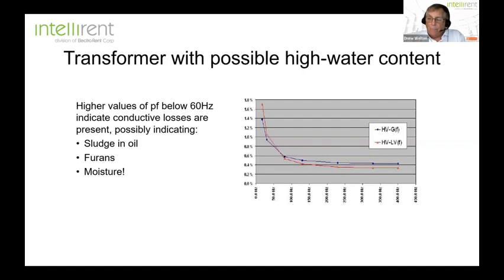your dissolved gas analysis shows an elevated amount of moisture. Okay, it shows a high ppm measurement. And let's say that your power factor also shows that you have conductive losses. Well, you could very well have a moisture issue. Okay, but we're going to take this testing one step further in terms of how we're going to really get a good indication. Okay, so let's take a look at this.